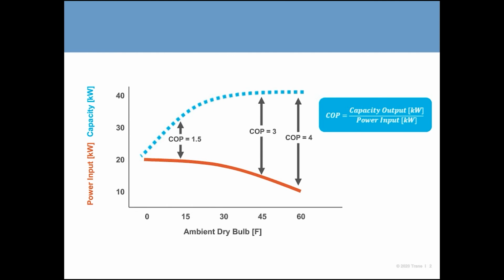A COP, coefficient of performance, is a ratio of what you get out versus what you put in. Electric resistance has a COP of 1. This is just a general example, not any specific equipment, but at 45 degrees in this example, the COP is 3. That means you get out 3 times as much as you put in. That's the big advantage for heat pumps over electric resistance. But you can see what happens as the ambient starts to go down. At 15 degrees, the COP is 1.5 because the power input went up and the capacity output came down. These types of performance curves from manufacturers are critical for designers because this is how you're going to size the equipment for your specific application.